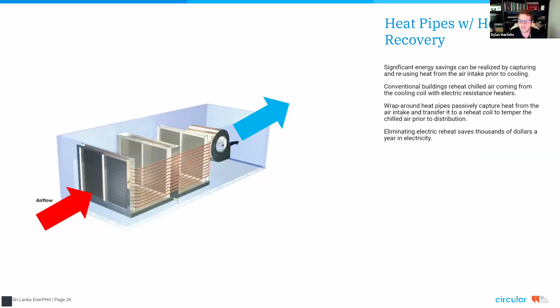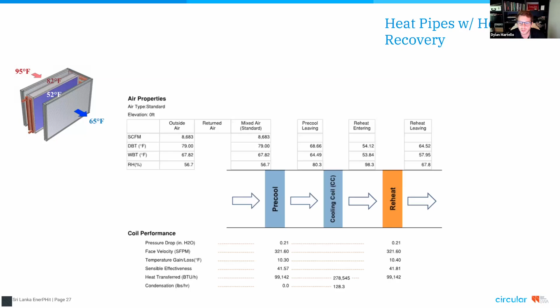If you go to the next slide, we have a good diagram to show this, from the specification of the unit. Again in degrees Fahrenheit, you can see the air starts out at 95 degrees, and then it gets pre-cooled by taking some of that heat and sending it to the reheat section of the unit, and the air drops down to 82 degrees Fahrenheit. Then it gets super-cooled down to 52 degrees Fahrenheit. Then that free heat that we stole from the air in the building brings that air back up to about 65 degrees Fahrenheit. That's very comfortable because it's also very dehumidified. It's not very humid air, and 65 degrees Fahrenheit is a very comfortable condition. Okay, next slide.